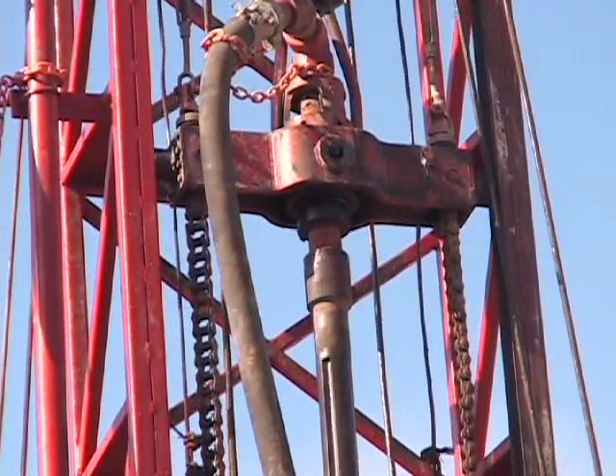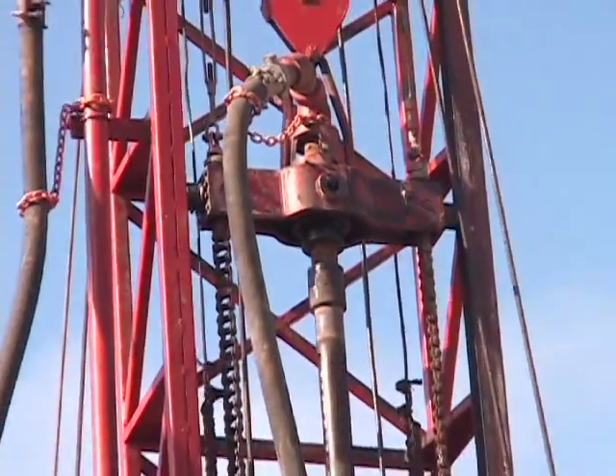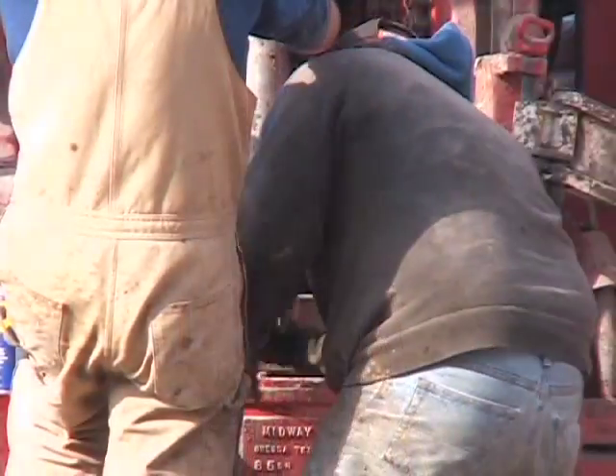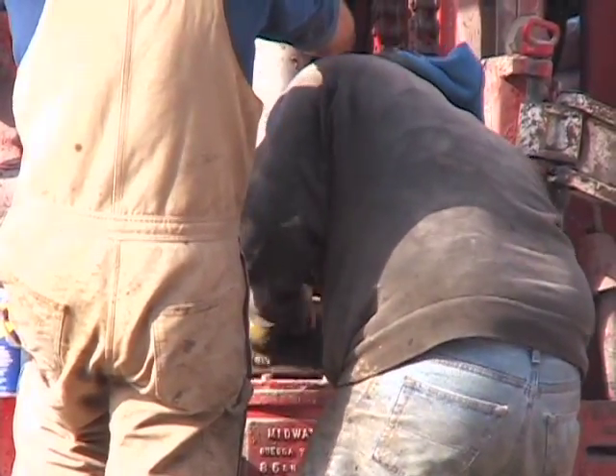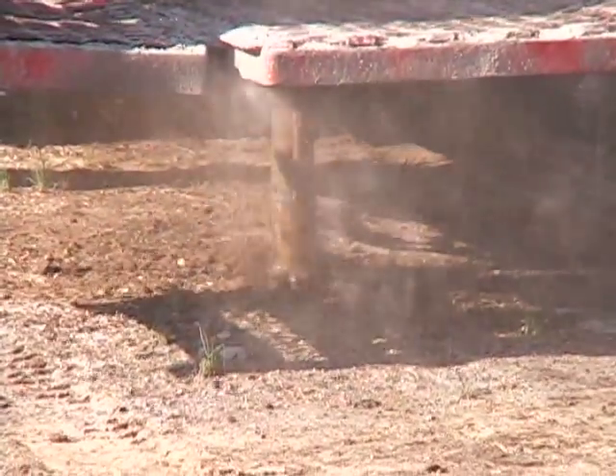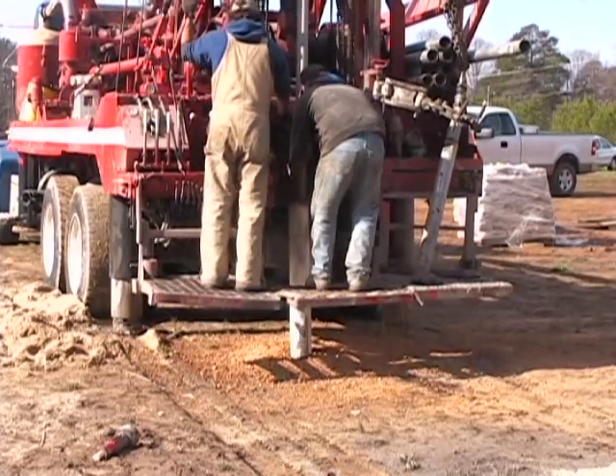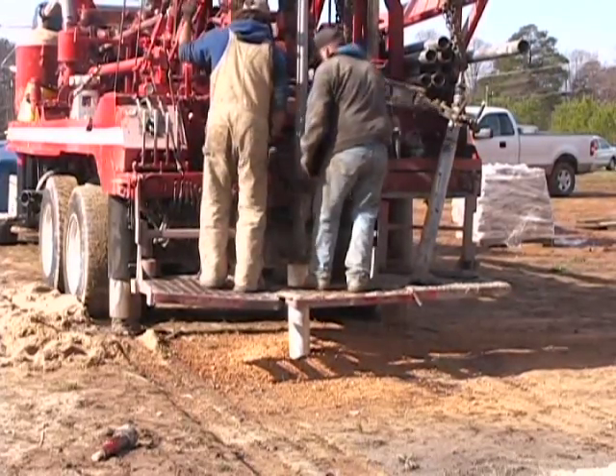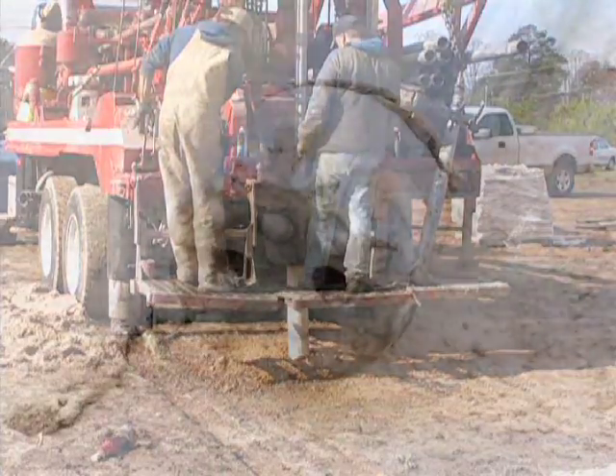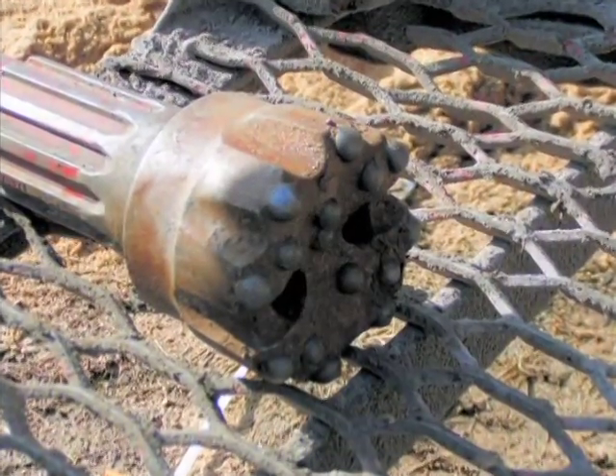The most common medium is the vertical loop. A truck mounted rotary digging rig is brought to the job site. During setup, the unit is leveled to assure a plumb hole is dug. A four and a half inch wing or cone bit is utilized to start the casing hole. After drilling four to six feet, the cone bit is removed, then a PVC pipe casing is pressed into the hole. Setting this casing stabilizes the ground and prevents surface cave-in from occurring.